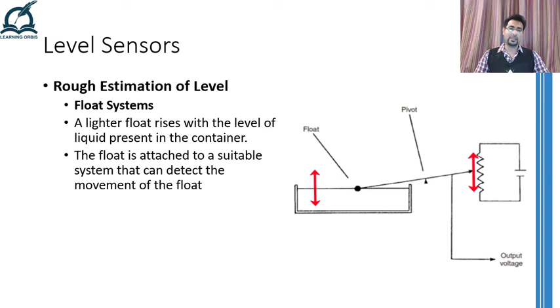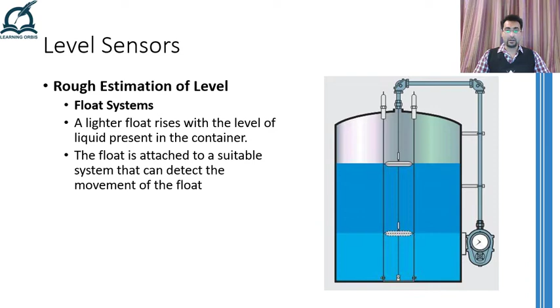In another configuration, the float is hung through a string, and the string, after going over some pulleys, is attached to a counterweight. As the liquid level rises, the float rises and the counterweight lowers. Whereas if the level of the liquid is lowered, the weight of the float is enough to pull up the counterweight. As this movement happens, the amount of rotation of the pulley can be measured through any rotational displacement sensor, which we already have discussed. And then this rotational displacement will tell us the level of the liquid present in the container.